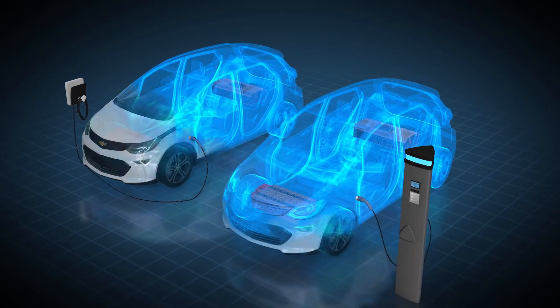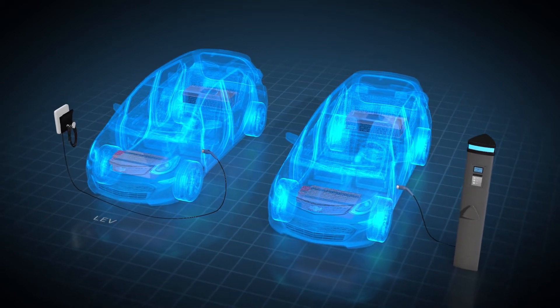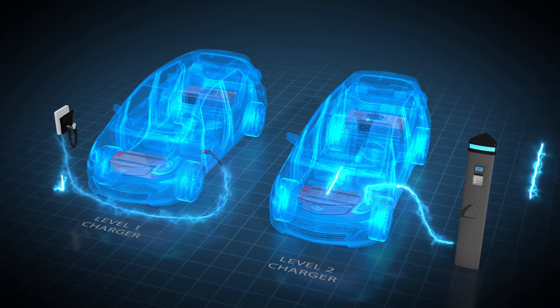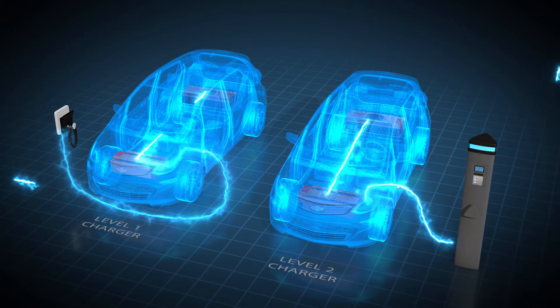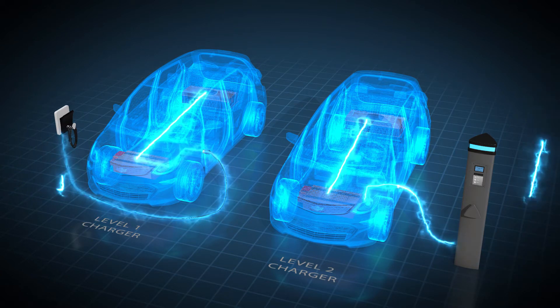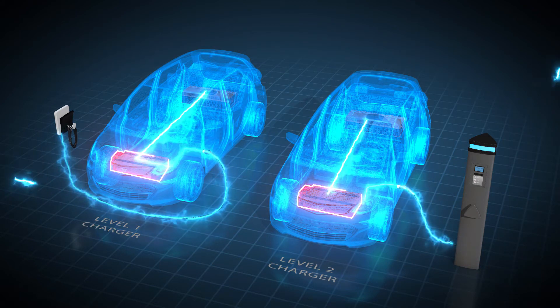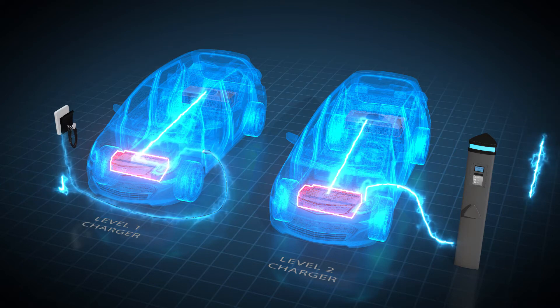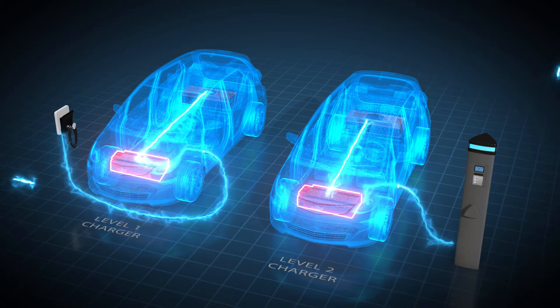The most common charging standards in the United States are AC Level 1 and AC Level 2, as defined by the Society of Automotive Engineers standard SAE J1772. Both AC Level 1 and Level 2 EVSE provide AC power from the grid to the vehicle through the same charging port. The vehicle's onboard charger converts the energy to DC power before it reaches the vehicle's traction battery. AC Level 2 EVSE is most commonly used in commercial applications and provides enough power for most Federal fleet and workplace charging.